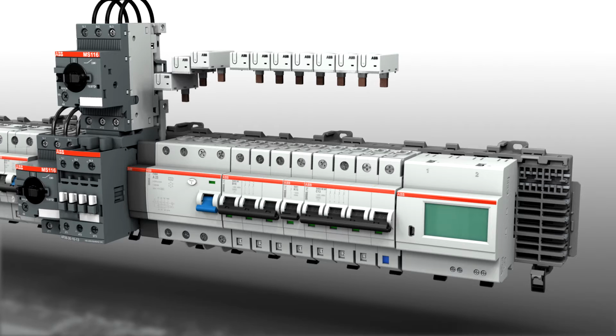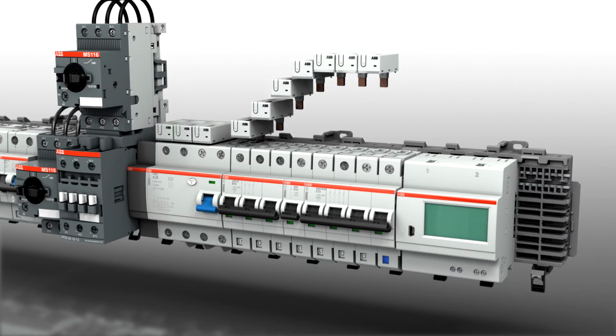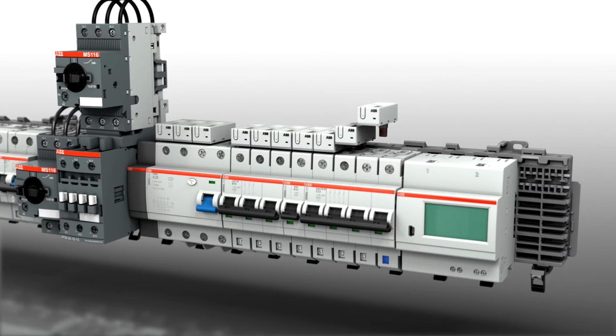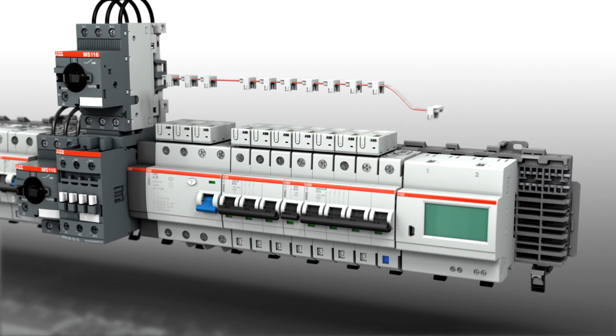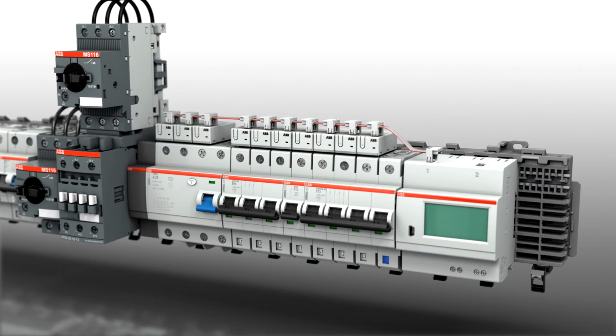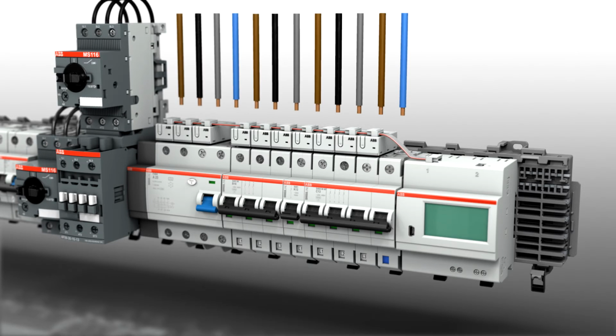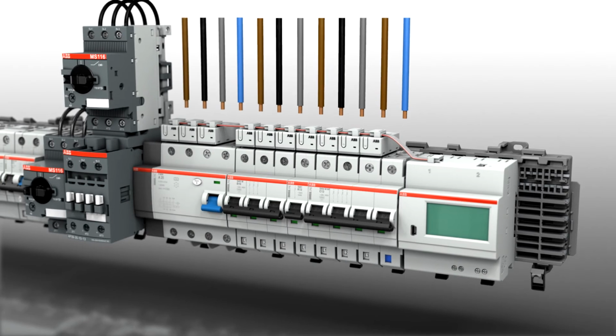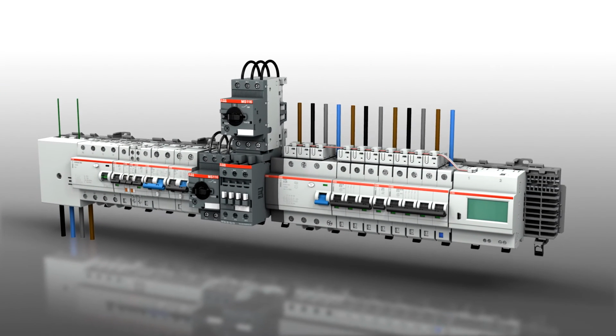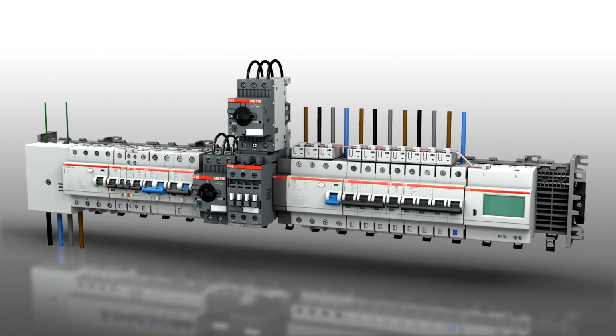A current measuring module can be fitted to the output terminals of the devices. This can be used to measure the current per output. The modules are connected to each other via a bus system. This enables overloads to be detected and possible failures prevented. SMISSLINE TP also enables a mixed pole arrangement of 1, 2, 3, or 4 pole devices.